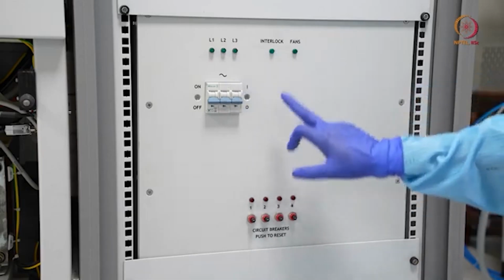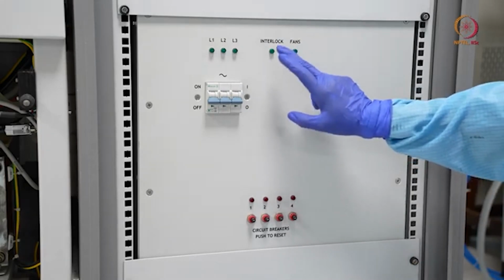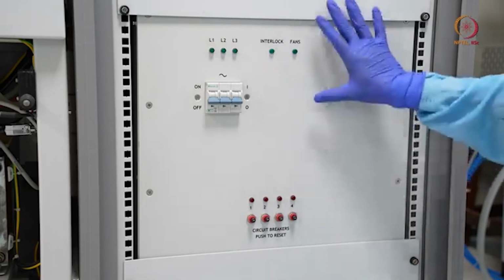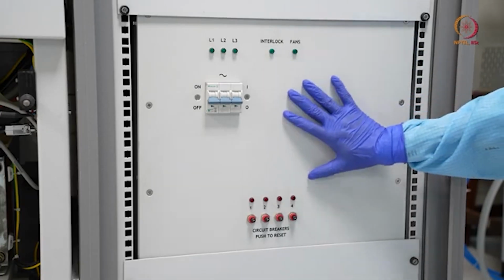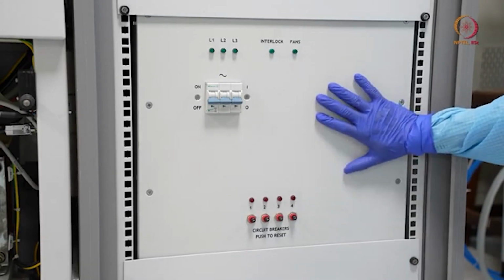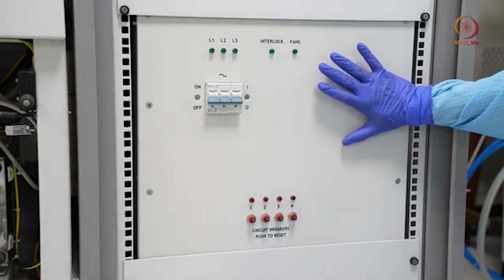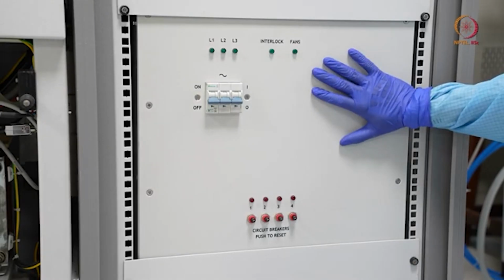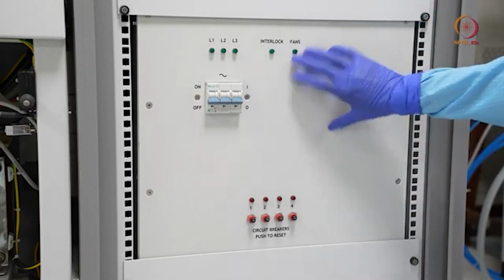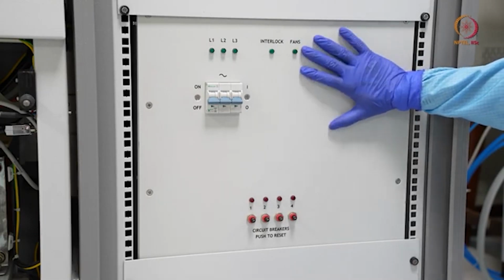So here you have to switch it on, and you can see here interlock and fan, these two are very important, because as long as all the interlocks are not met, the output of this transformer will not come, as this is a 5 kilovolt system, the output of this transformer is 5 kilovolt. So it can give you an electrical shock hazard. As this is very hazardous, you cannot even take it out without opening the other parts. And the fan is required to cool down the area. So this is the basics of this.